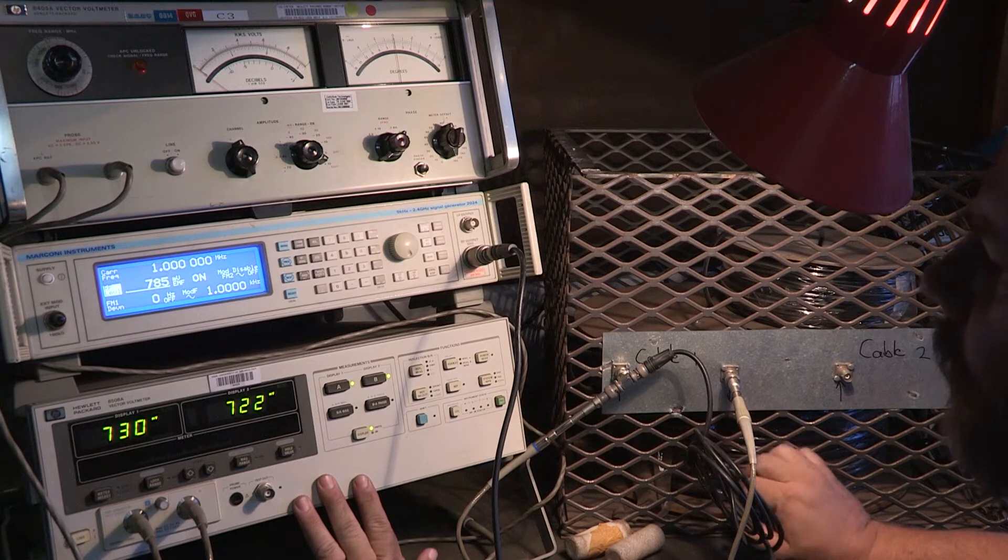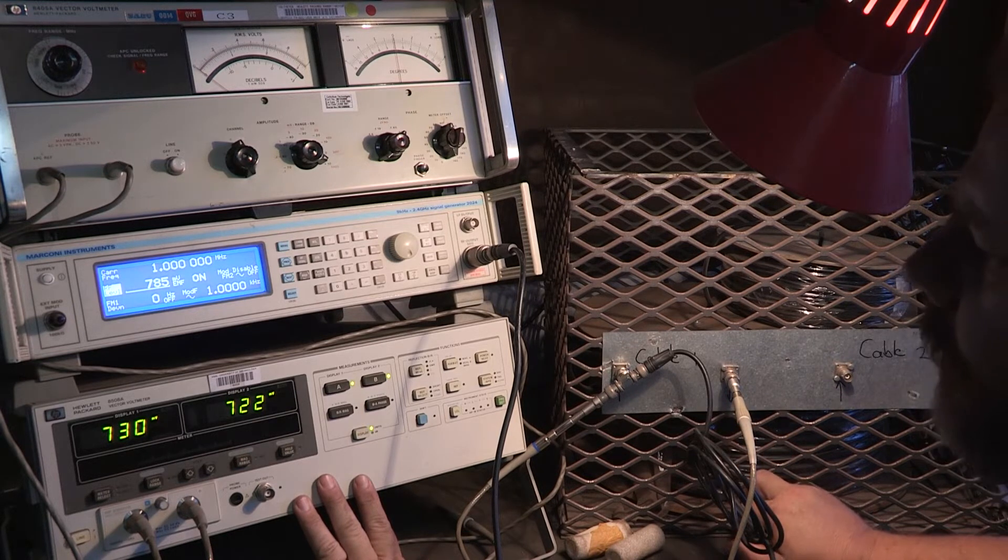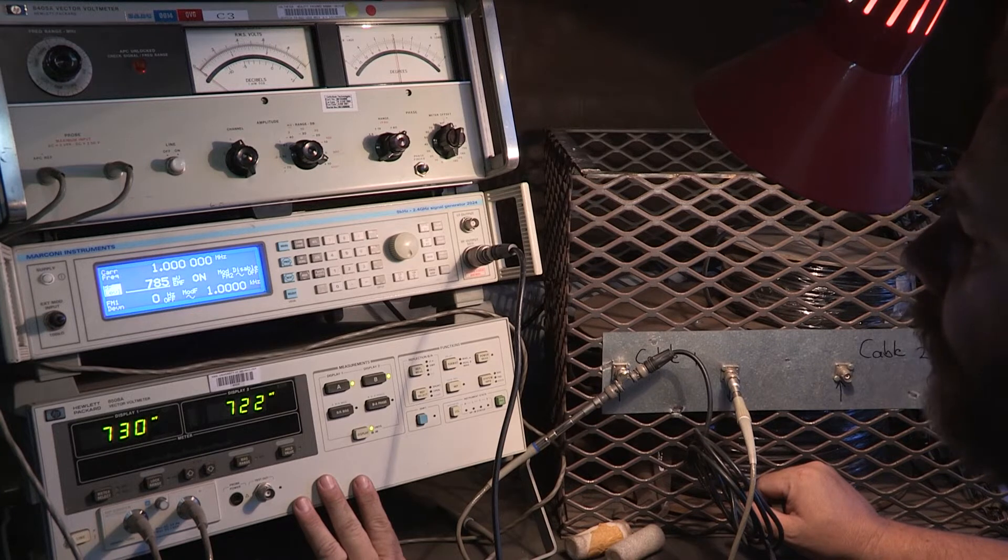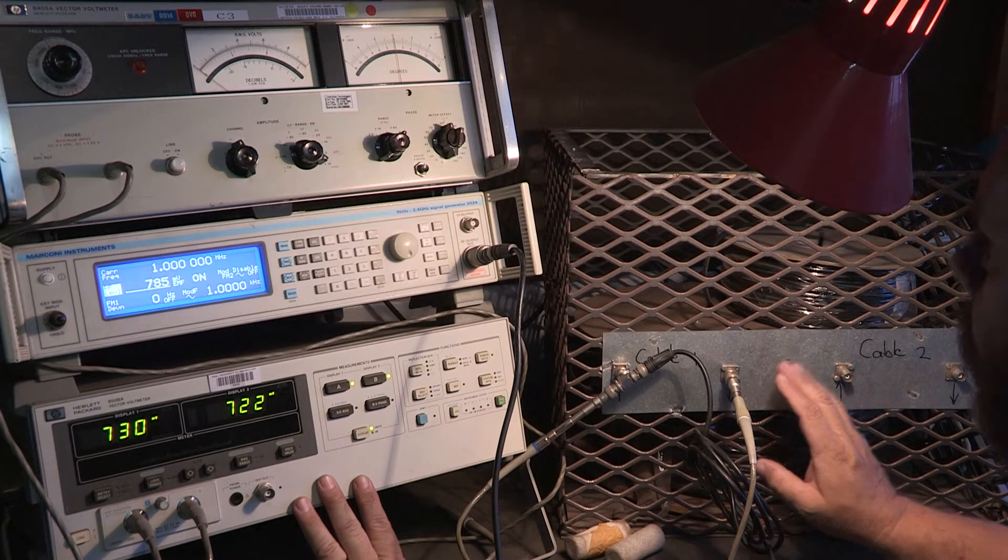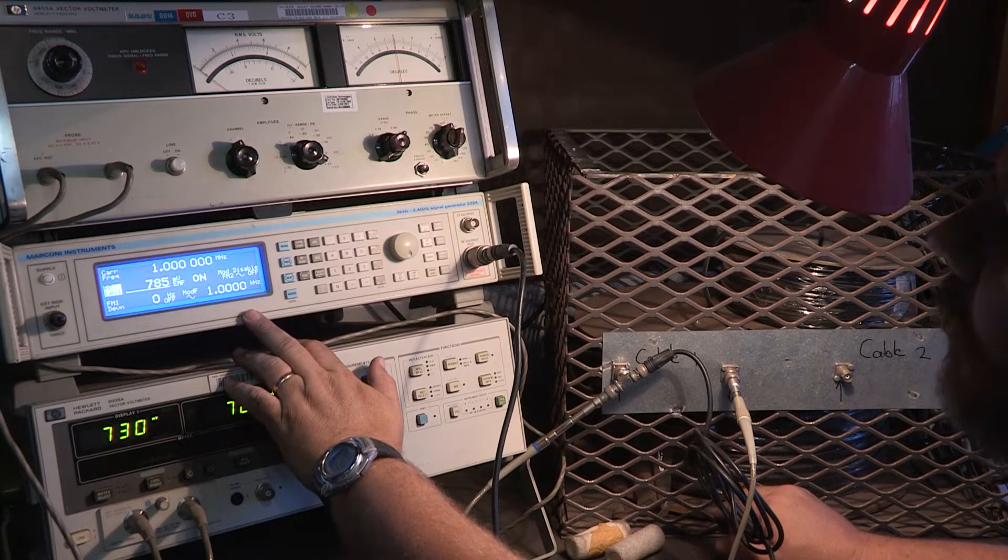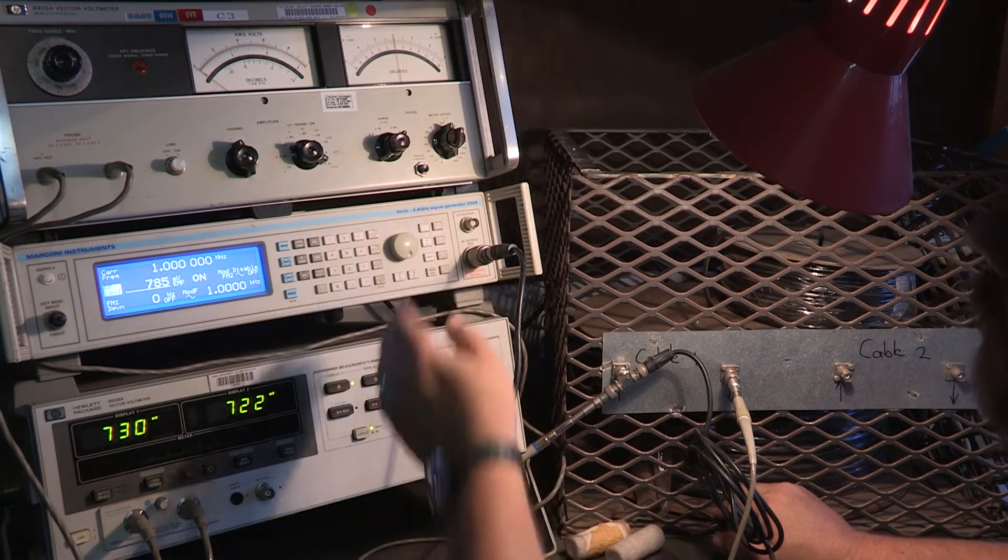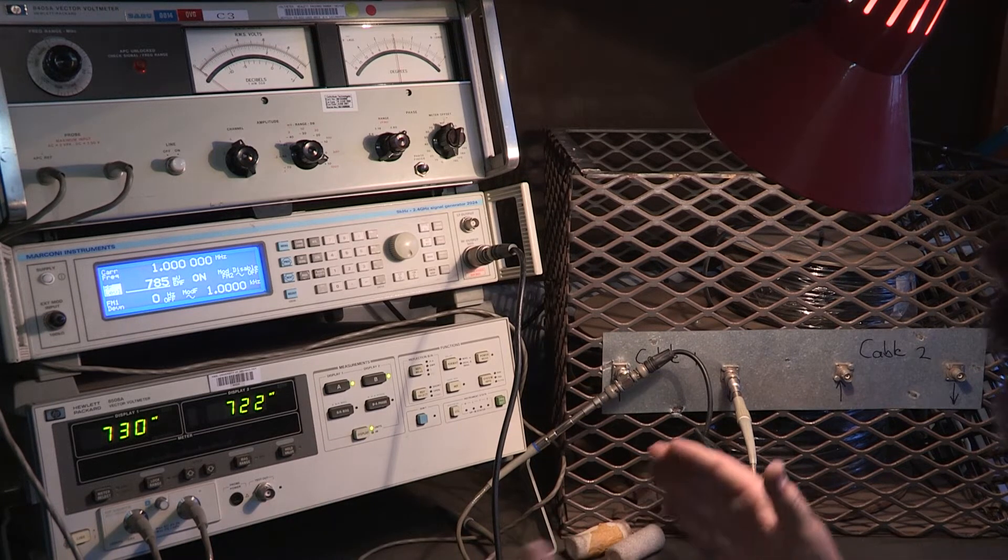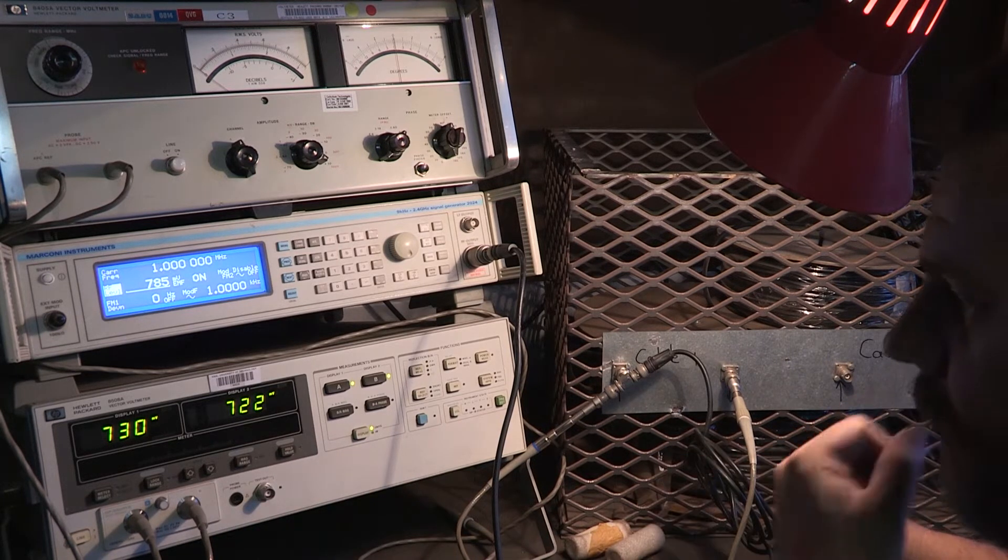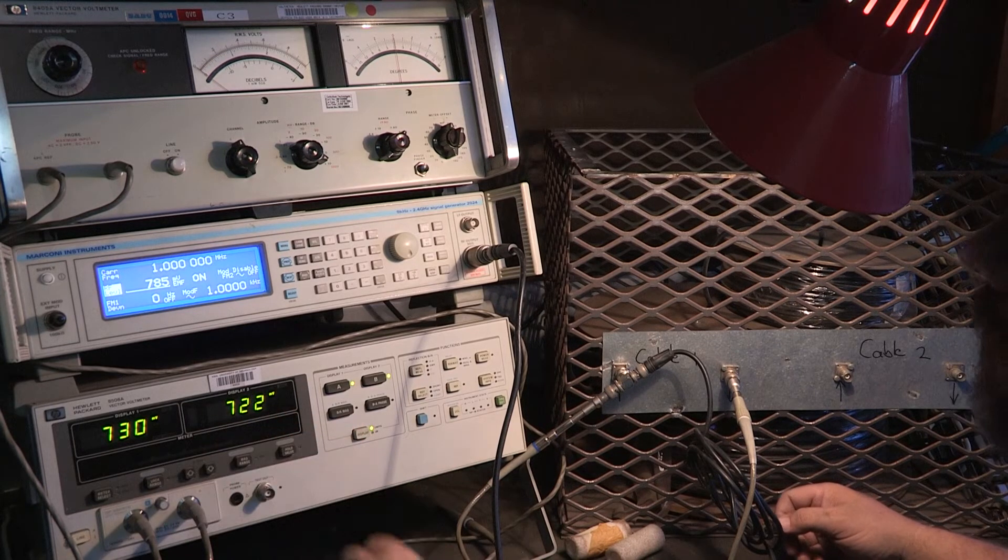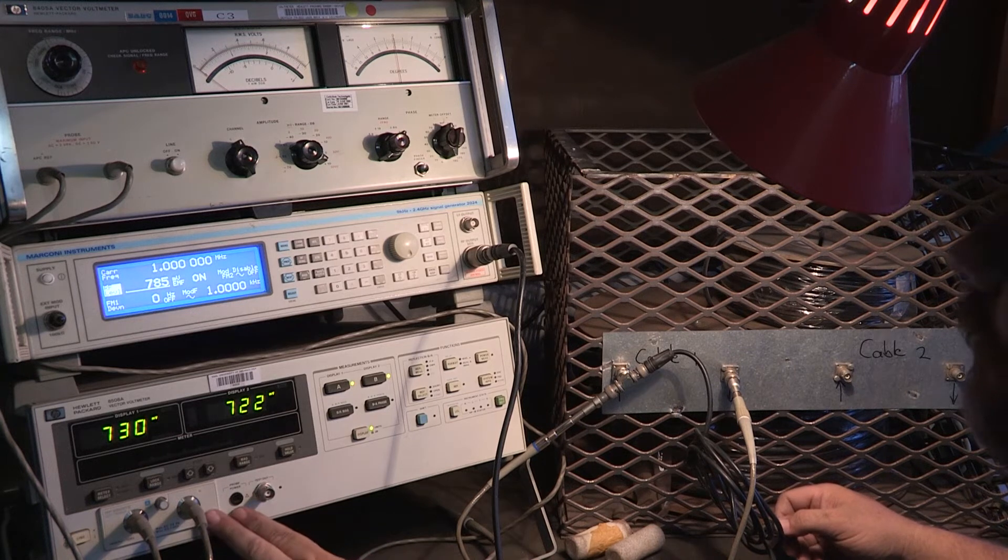The setup is very simple. I've got a vector voltmeter, which is a special voltmeter for measuring voltages across a range of frequencies. And then I have a radio signal generator that can go up to 2.4 gigahertz. We're going to choose certain frequency intervals, and at each frequency interval, take down the reading here.